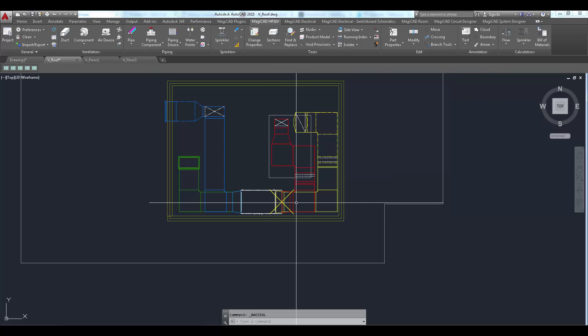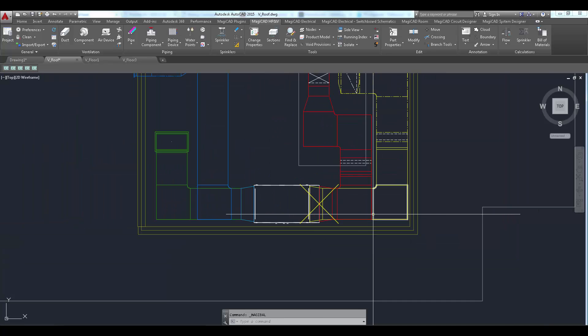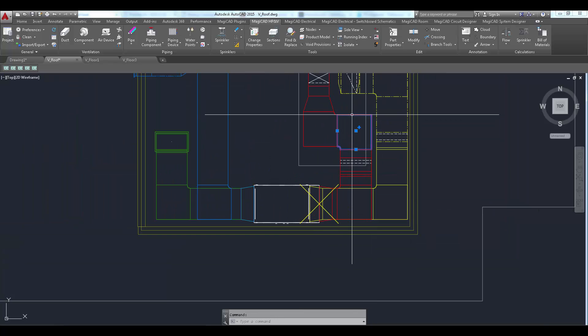Notice that the calculation gives a warning that the air flow is under recommended minimum value. This means that the air handling unit should be updated to correspond to the new working point.